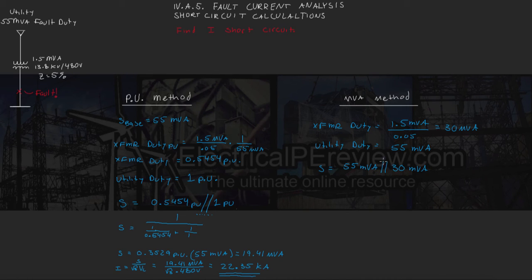Another easier way to carry this out, we're going to do it this time below. I didn't do it over here just to make sure everyone was following along, but a much easier way to carry this out, is you actually first multiply the two terms, so 55 MVA times 30 MVA, and then you divide by the sums. So 55 MVA plus 30 MVA.